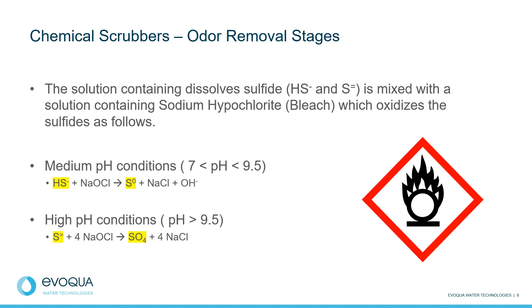Over time, though, the elemental sulfur that is generated in this reaction can start to build up on the packing media inside the system. Because of this, we will need to routinely acid wash the equipment to remove any built up solids that might eventually reduce overall efficiency.